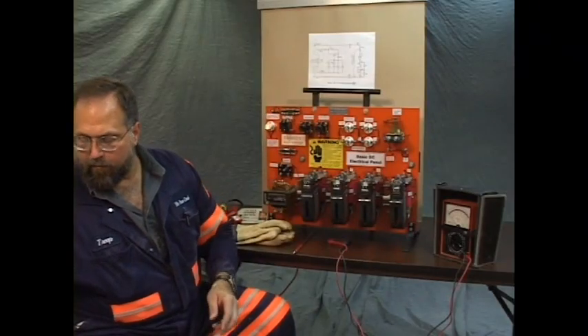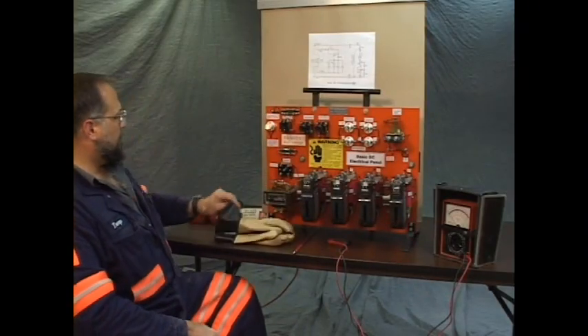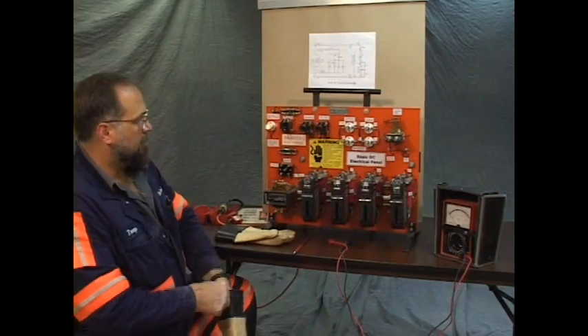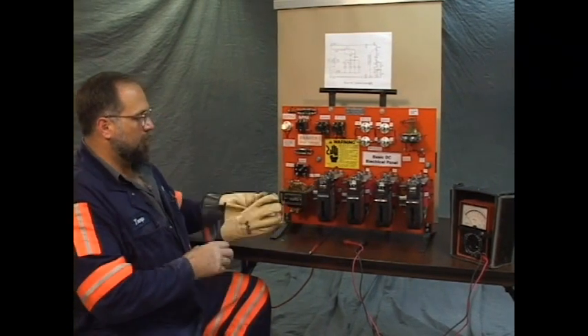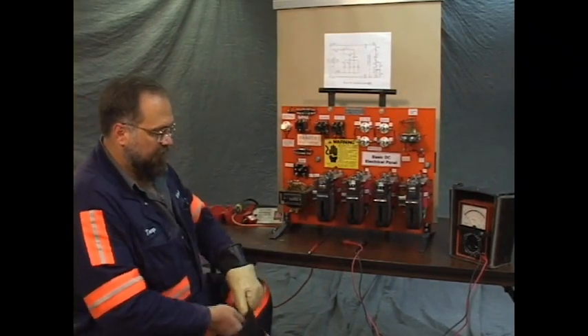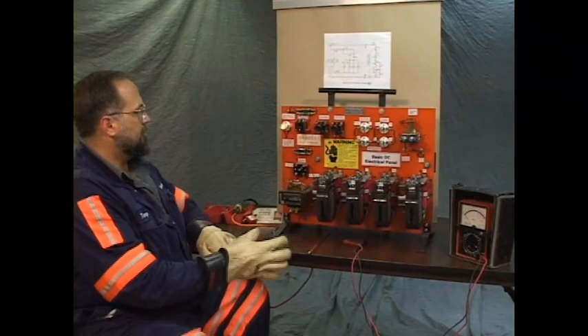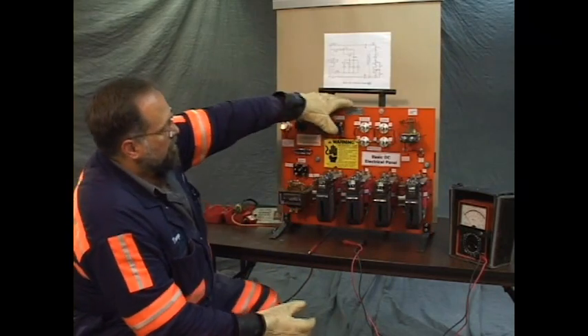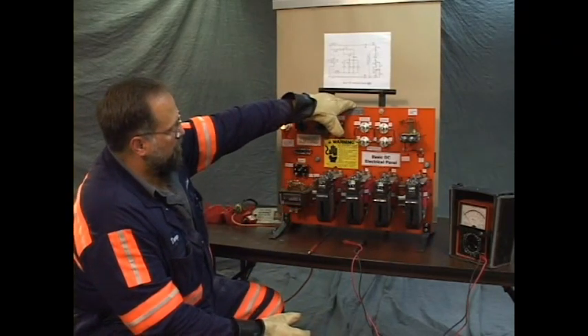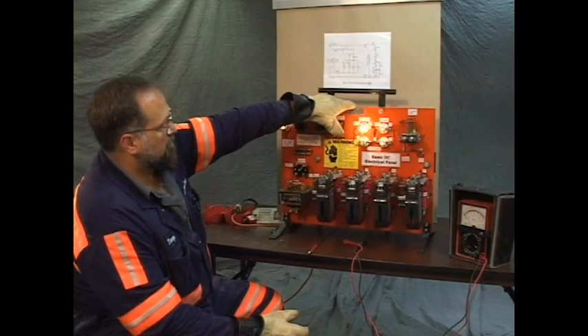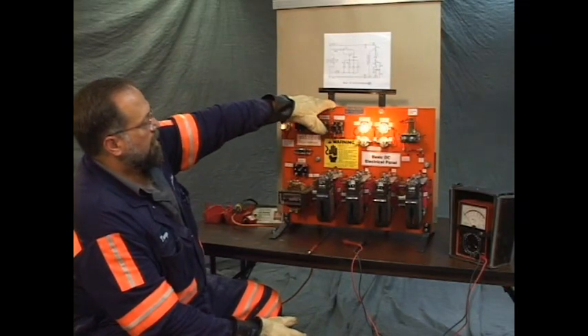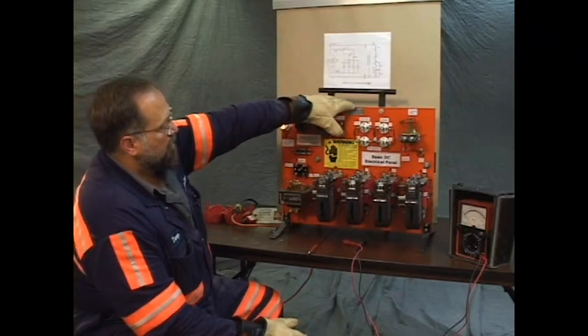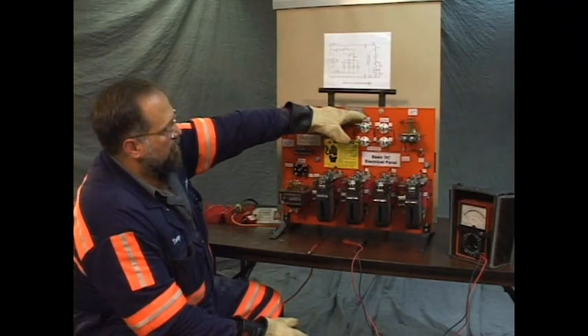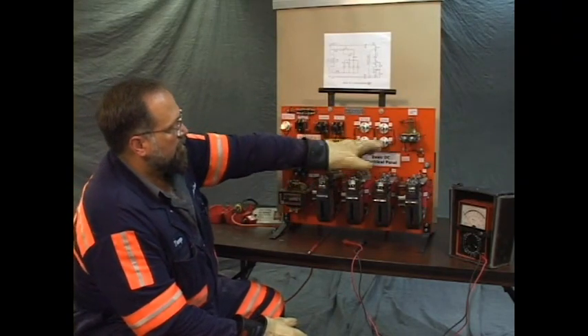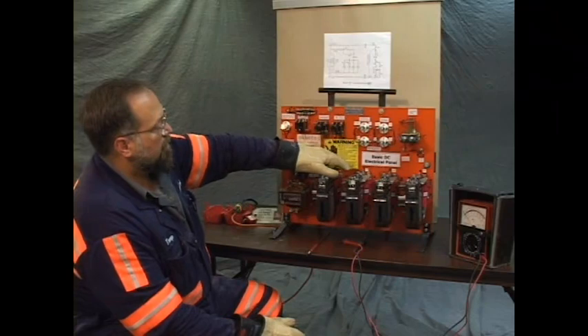Well, let's glove up here and put our panel through the paces and show them normal operation to have everyone refreshed on that. Normal operation is as follows. Press the start switch, click, click, click. You'll note you have 4 lights. Note the pattern of the lights.